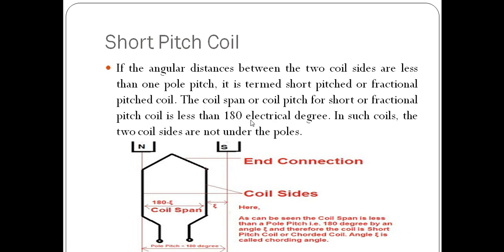In a short pitch coil, the coil span or coil pitch will not be equal to 180 degrees; rather, it will be somewhat lesser than 180 degrees. In this figure, you can see the coil sides are not under the poles of the machine — this coil side is under the north pole, but this coil side is not under the south pole. So the coil span or coil pitch will not be equal to one pole pitch; it is lesser than one pole pitch. The angle by which the coil span is less than 180 degrees is known as chording angle.